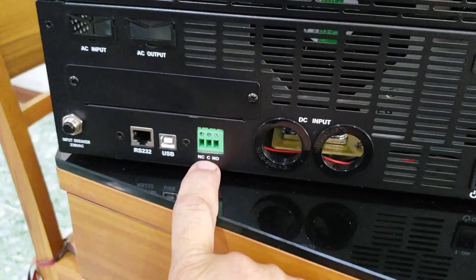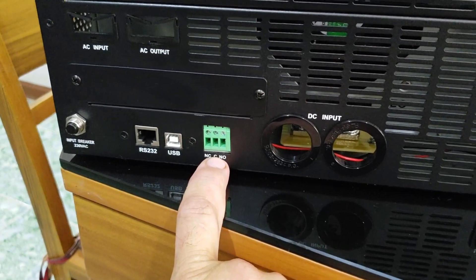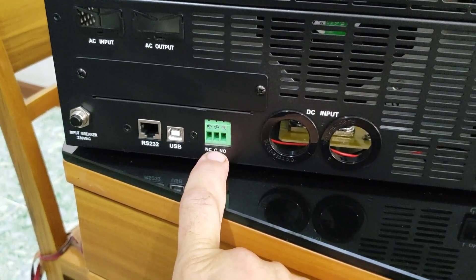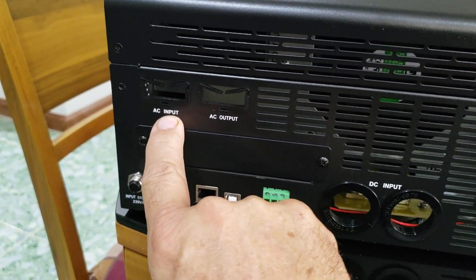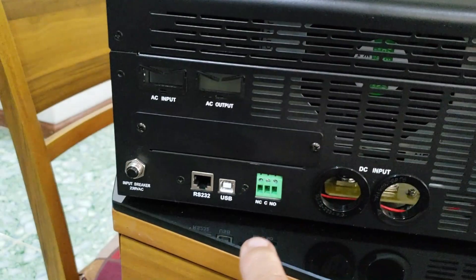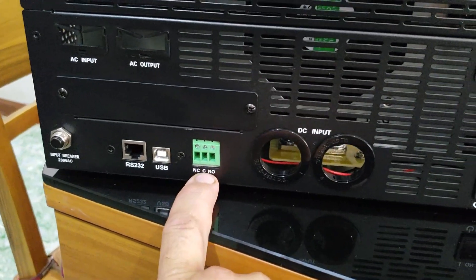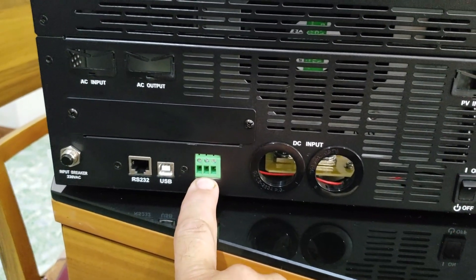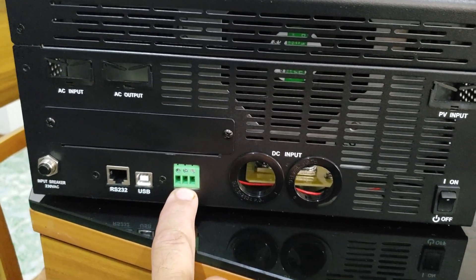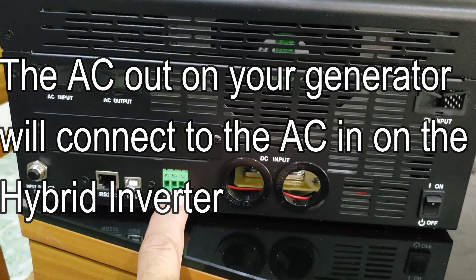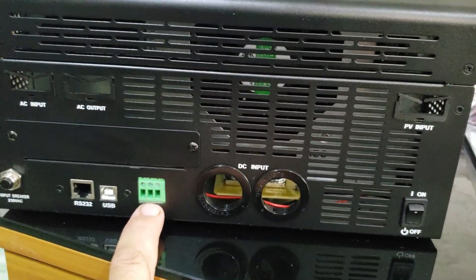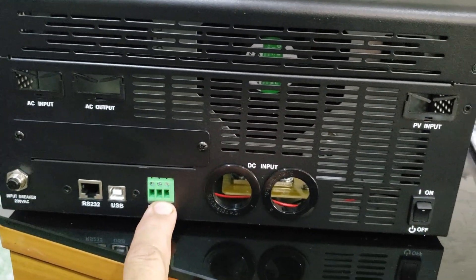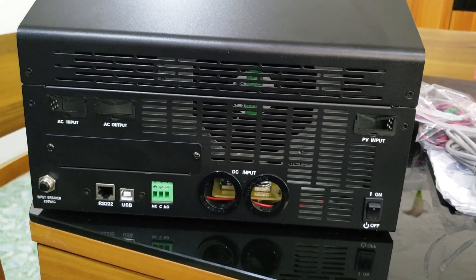You see this connector here. This is for connecting this to a generator. And so if you got a dry contact switch once again if you don't want to use this AC input is a backup off the grid and you're completely off grid. But you have a generator and that generator has a dry contact switch that can start it. This will crank up your generator charge your battery bank off the generator when it's full it'll shut it back off. Or if the clouds clear away and your PV array starts putting out enough power and it sees it's charging it sufficiently it'll turn your generator back off.